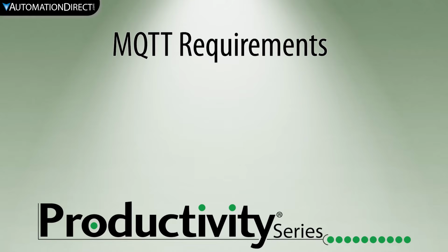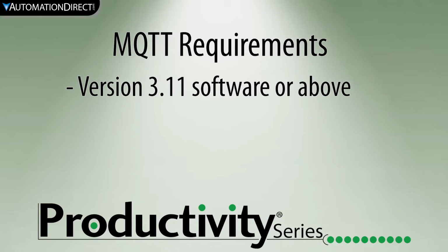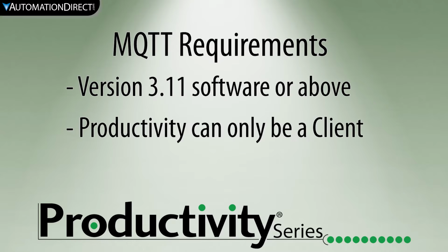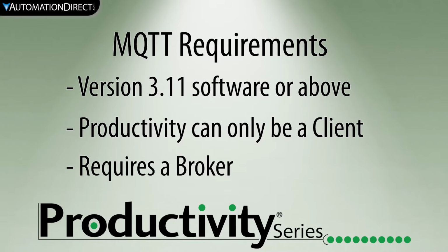To set up MQTT on your Productivity PLC, you must have version 3.11 software or above. The Productivity can only work as a client. You must have already set up a broker to handle the messaging. There are too many brokers, and their setups are way too varied to cover in this video. Please see MQTT.org for more information on this topic.